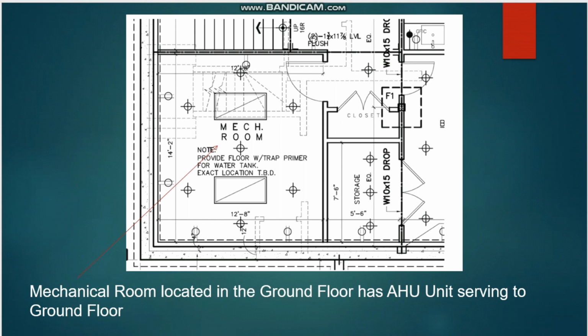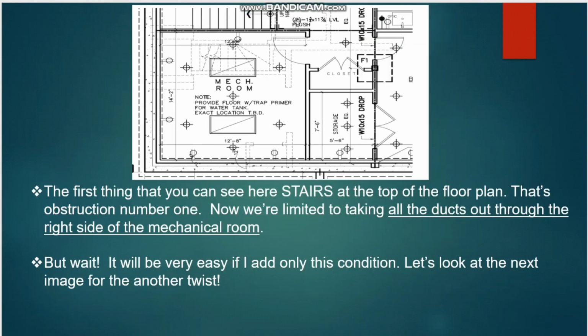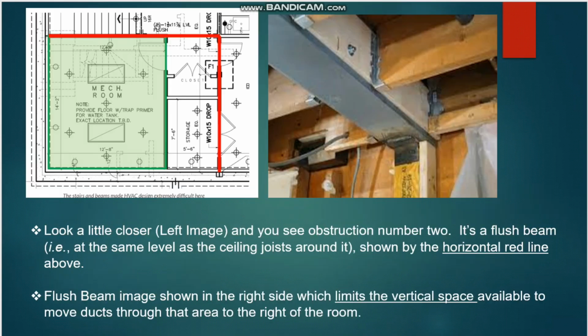So here you can see we have a mechanical room located on the ground floor, which has the AHU unit serving the ground floor. The first thing you can see here is the stair, at the top of the floor plan. That is the important obstruction number 1. So now we are limited to taking all the duct out through the right side of the mechanical room. We cannot take any duct through this side or here. All the supply duct and all the return duct we have to take to the AHU through the right side of the mechanical room.